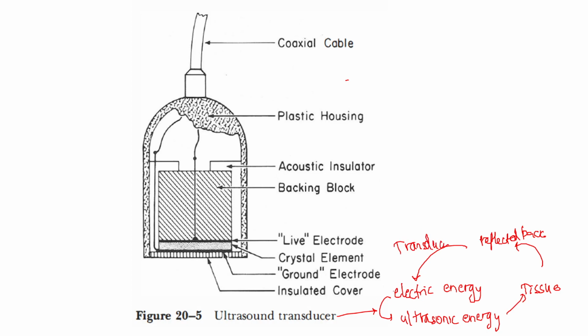Okay, the most important thing in this transducer is the crystal element. This crystal element is actually a piezoelectric crystal element, and this crystal element is located near the face of the transducer. The front and back of the transducer is coated by thin conducting film, and it is in contact with the live electrode and ground electrode. It is in contact with two electrodes. The electrode on the outside is connected to the ground, so it is called the ground electrode.